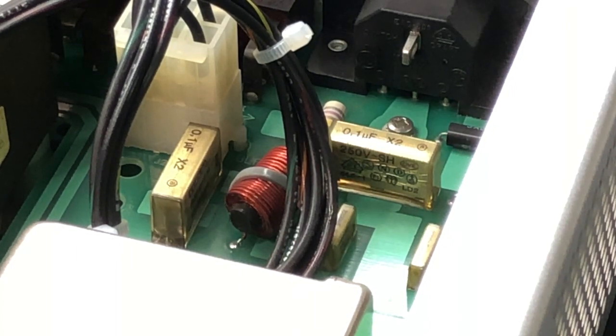But the manufacturer didn't anticipate them failing with cracks in the case, that type of failure mode. So when you see these older capacitors, they really need to go whether they have cracks or not, because they'll definitely crack over time even if they appear okay when you see them. At 30 some years old, they're basically at the end of their useful life. Now, the ones in my previous video had some minor cracking, not nearly as much as these, so it does vary.